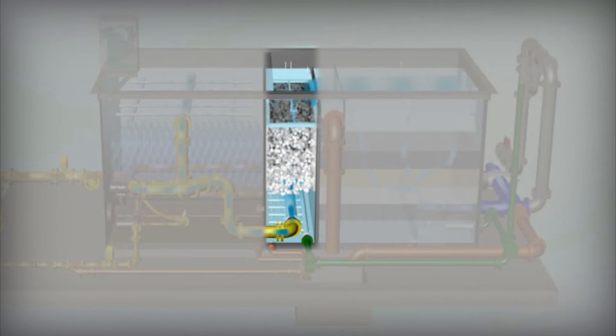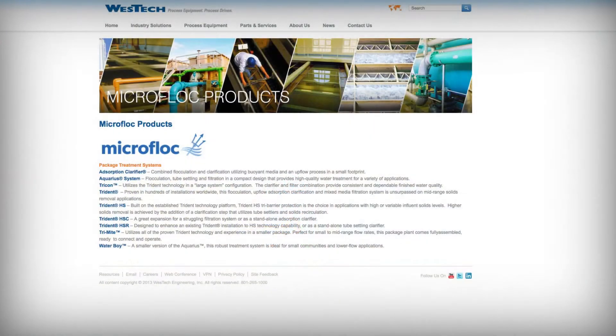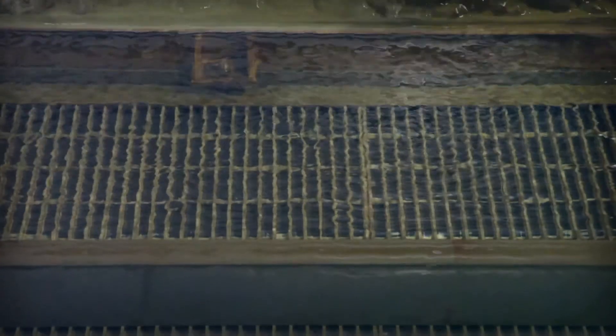The second stage in the Trident HS system is the patented adsorption clarifier developed by Microfloc products. Non-settling solids are retained by the buoyant media, which reduces the load on the mixed media filter, extending filter-run length and reducing backwash waste volumes.